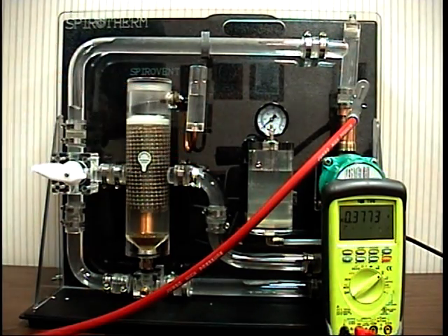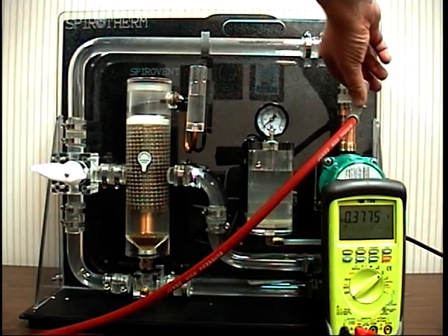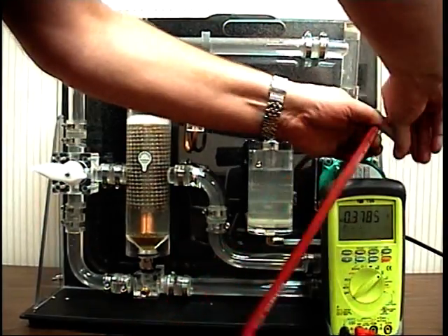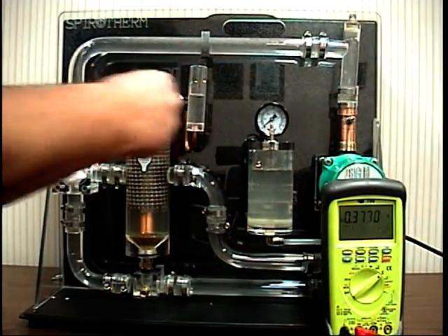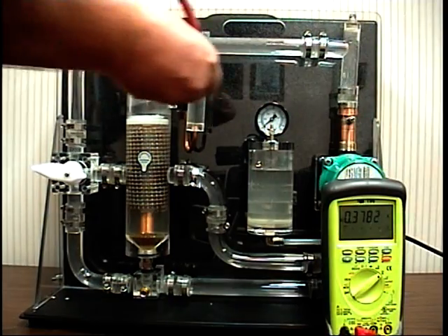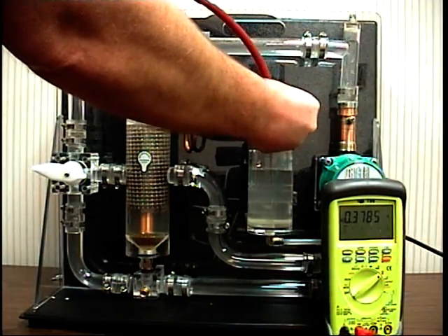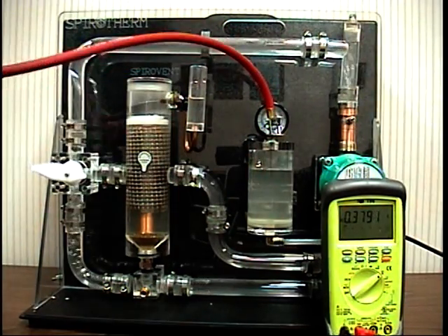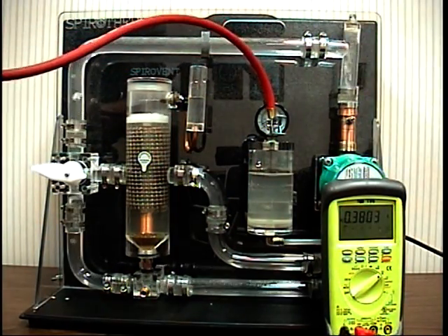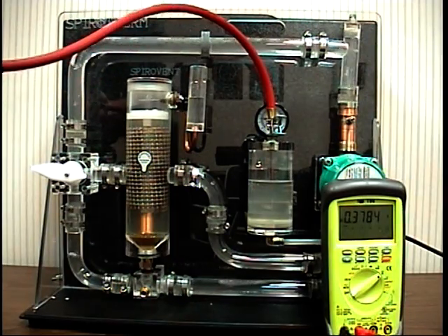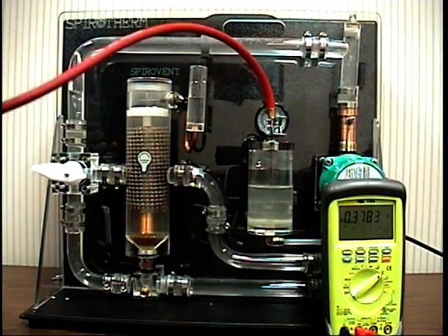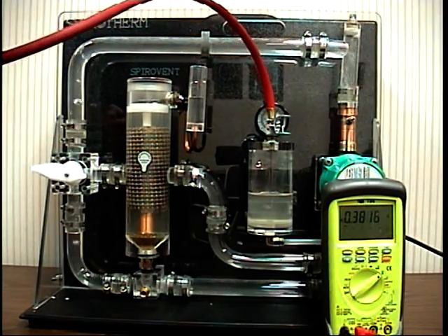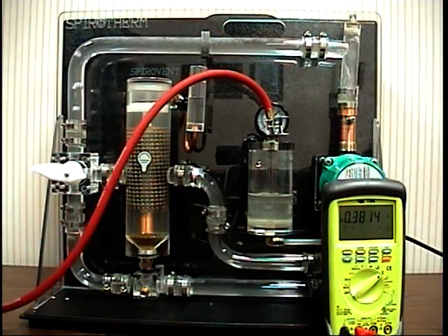Right now our system pressure is set at 0 pounds of pressure. I'm going to take the fitting off here that goes into the system and inject air in. I'm going to go to the expansion tank. Right now the pressure of the expansion tank is 0 pounds. So I'll inject a little bit more air into the top of the expansion tank, start compressing it, and add a little bit more pressure into the system. Okay, there's about 10 pounds of pressure in the system.